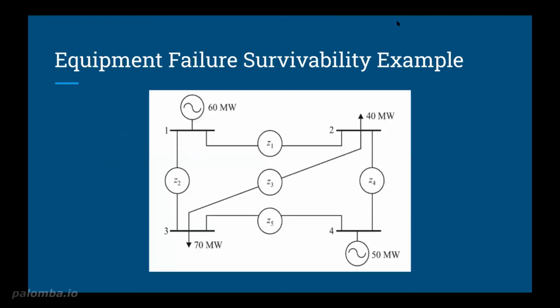So after those examples, now this is a specific example that we'll be evaluating in detail in our final report. As stated before, observability analysis determines if the received measurements are sufficient to estimate the state of the system. This determines the solvability of the system under state estimation. And although modern PMU and communication technology use is limited, here we are going to assume that all of these economic challenges associated with this are a non-issue. Additionally, we're not going to be addressing the challenges associated with the computational resources required for performing state estimation dynamically in real time for this system.